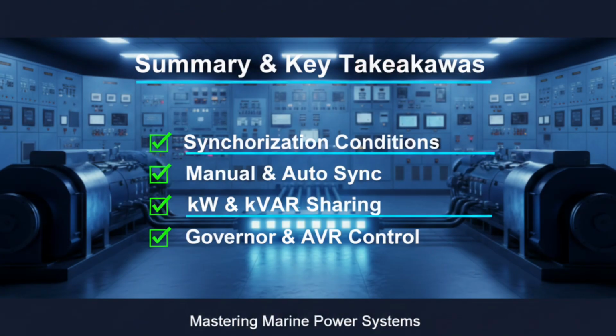Summary. Let us quickly summarize this lecture. Synchronization ensures safe connection of generators to the busbar. Four conditions must match: voltage, frequency, phase sequence, phase angle. After synchronization, load must be shared properly. Active power is controlled by governor. Reactive power is controlled by AVR. Manual synchronization requires skill. Automatic synchronization uses PMS. Understanding these principles is essential for marine engineers and ETOs. Safe synchronization means safe ship operation. Now you clearly understand how generators operate.